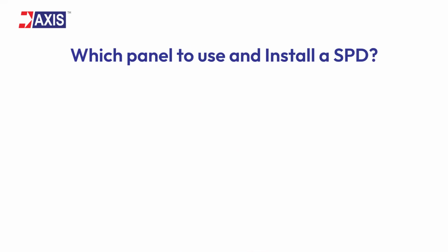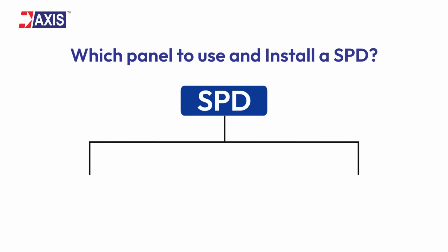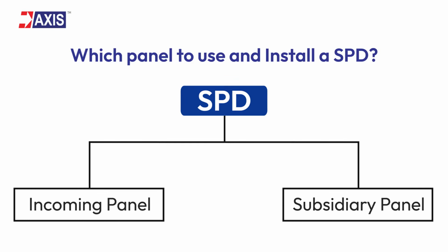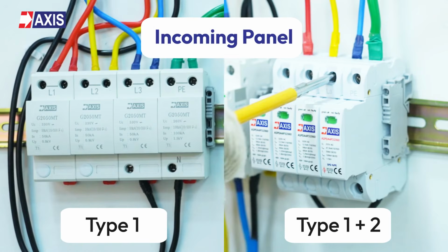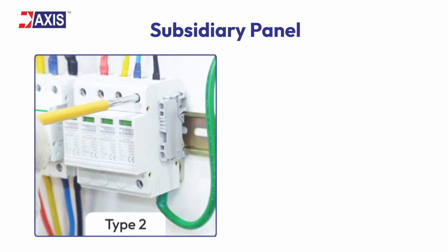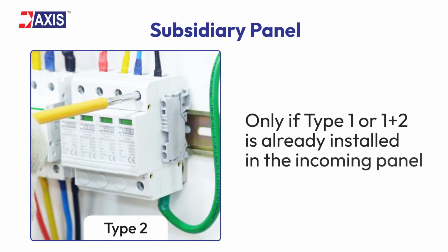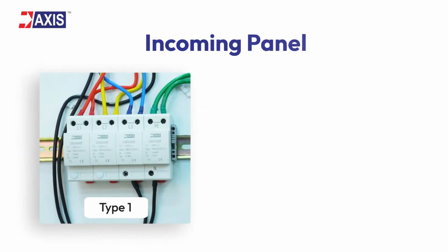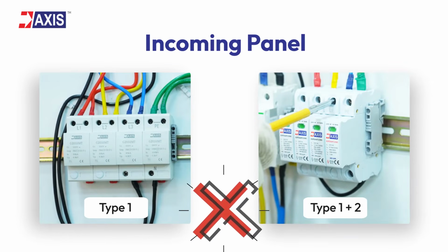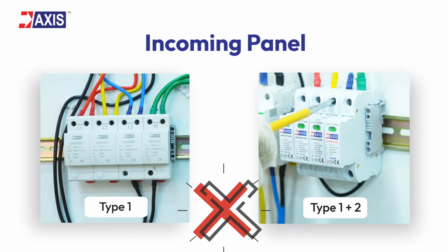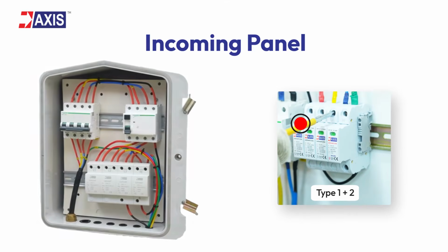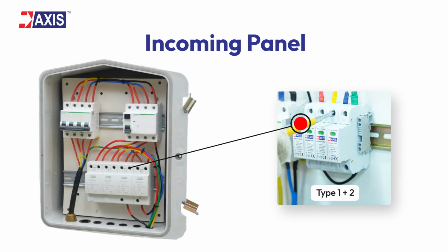Next, let's select a panel. You can install SPDs in the incoming or subsidiary panels. For the incoming panel, use Type 1 or Type 1 plus 2 SPDs. For the subsidiary panel, use Type 2 SPDs, but only if Type 1 or Type 1 plus 2 is already installed in the incoming panel. In case no Type 1 or Type 1 plus 2 is installed in the incoming panel, you will have to install Type 1 plus 2 directly in the subsidiary panel. Here, we are installing it on the display board.